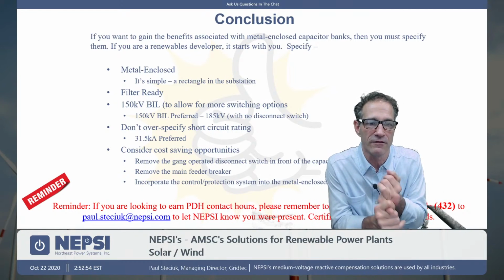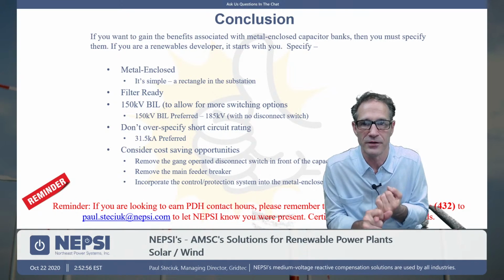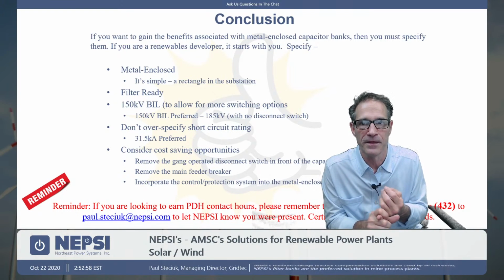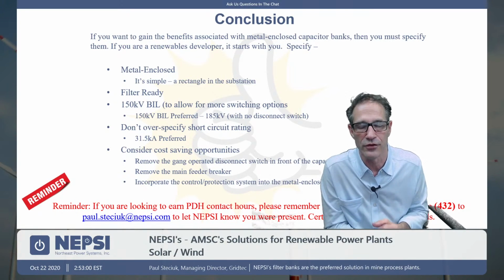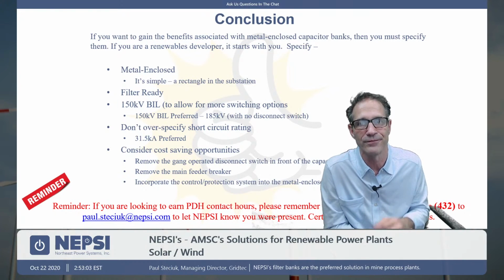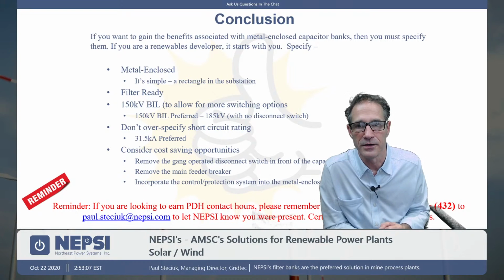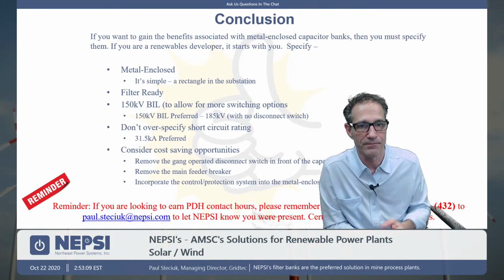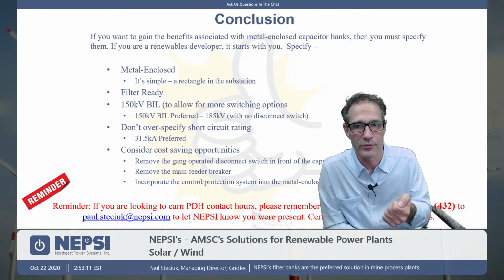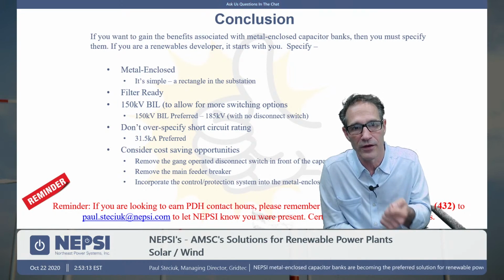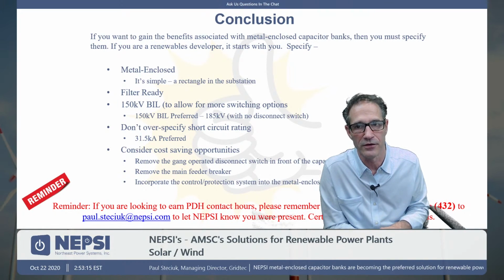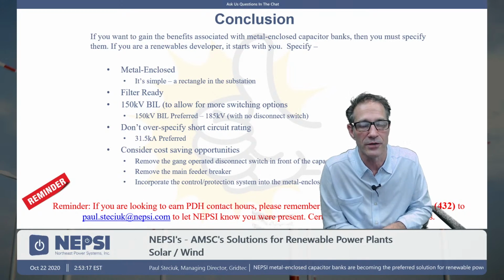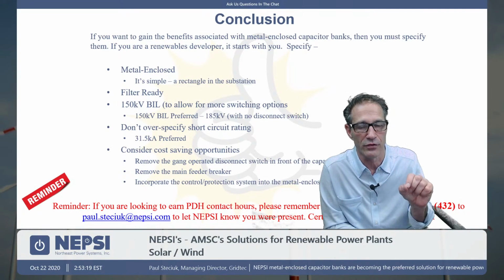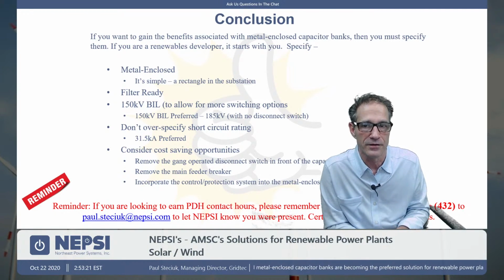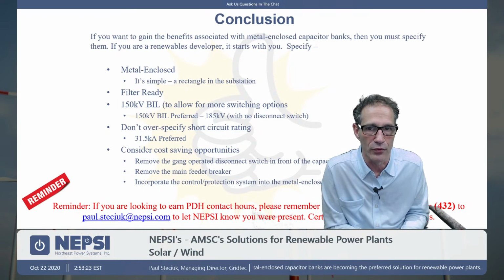When we specify filter ready, okay, it's going to come at almost no cost, and it's backup insurance for the developer. If you got a resonance issue, Filter Ready is going to take care of you. If you have a utility that's putting on a meter at the point of common coupling, there's a very, very good chance you could potentially fail IEEE 519 at the point of common coupling, especially at high frequencies or at one frequency. So having a backup plan is very important.